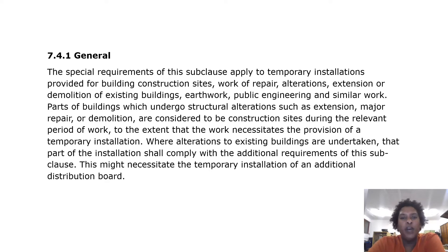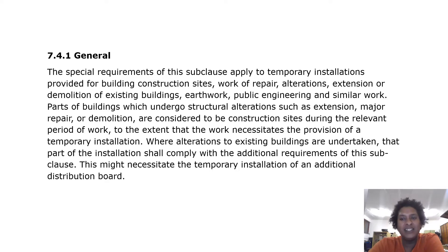General. The special requirements of this subclause apply to temporary installations provided for building construction sites, work of repair, alterations, extension or demolition of existing buildings, earthwork, public engineering and similar work. Parts of buildings which undergo structural alterations such as extension, major repair or demolition are considered to be construction sites during the relevant period of work, to the extent that the work necessitates the provision of a temporary installation. Where alterations to existing buildings are undertaken, that part of the installation shall comply with the additional requirements of this subclause. This might necessitate the temporary installation of an additional distribution board.